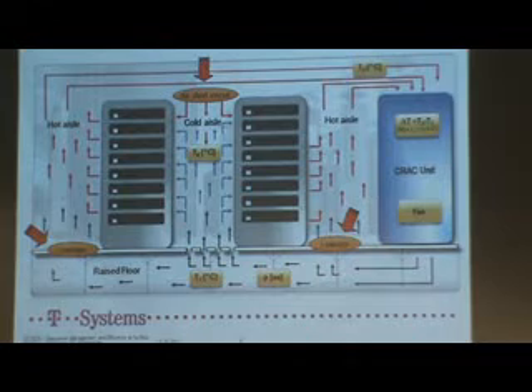So if we have a look at a normal data center, in normal data centers we should have a cold and a hot aisle structure as a rule. And what is most important here is the server inlet temperature. To achieve the server inlet temperature, you have a CRAC unit and a fan. And even if you have this system set up, you have some weak points in your data center. One weak point is leakage in the raised floor, usually arising from feed-throughs for network and power cabling on the back-end side of the racks. What's happening here is that you have cold air coming to the hot aisle. So we are cooling the hot air, which makes absolutely no sense. And you also have some short circuits of the air, which is sucked in from the cold aisle again, and so it's also very inefficient.